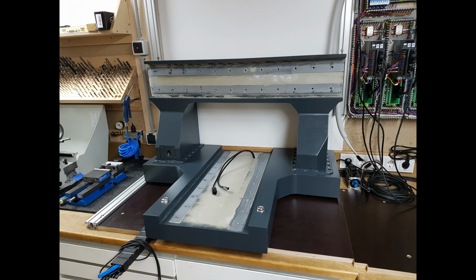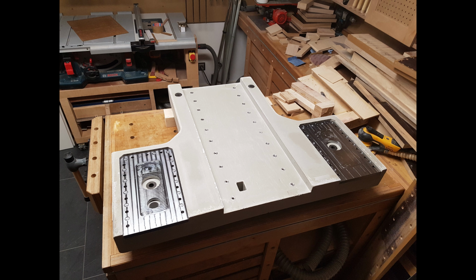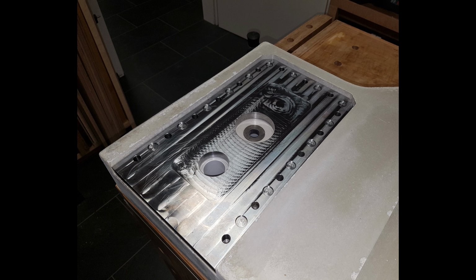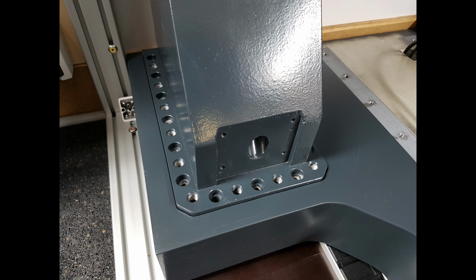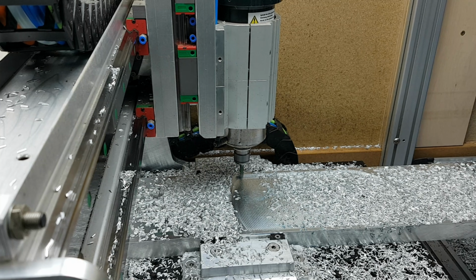The gantry side pillars have at the bottom steel plates cast into them, which rest on matching steel plates in the base. The gantry is fixed to the base with M8 bolts through both plates. The gantry plates have in addition a pattern of M12 threads for set screws, and the entire tramming of the gantry is done with them.